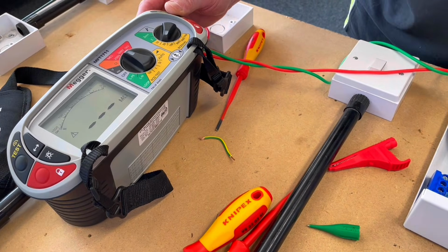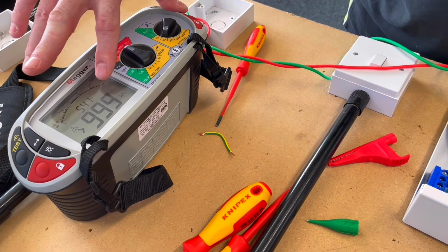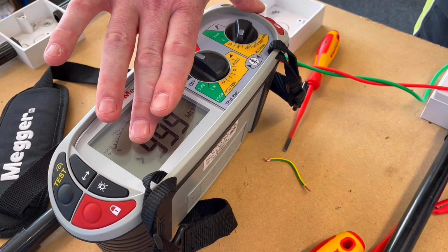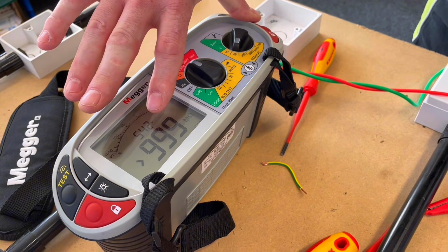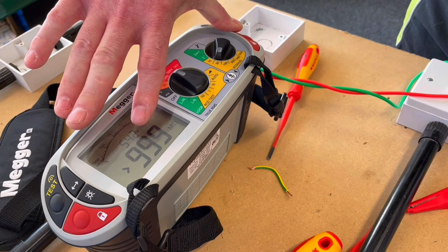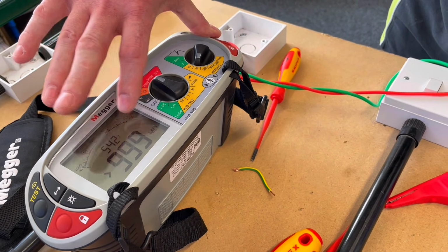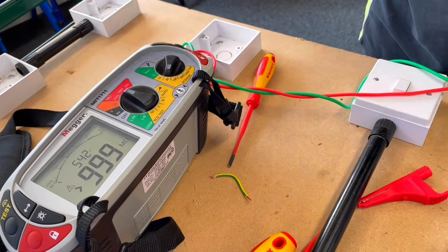I want to press my test button. I need to press and hold it. I've got a reading greater than machine can read, greater than 999. The symbol on the end is the greater than. I like to put plus in my test paperwork, so I would put plus 999 megohms, often called megaohms. So that's the first one.